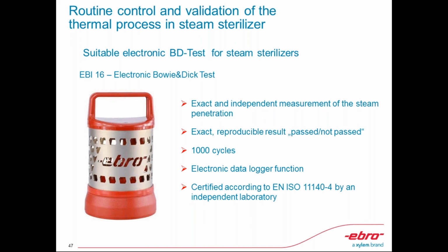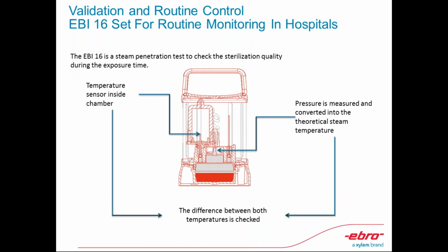And it is certified according to ISO 11140-4 by an independent laboratory. So the Bowie and Dick test logger, the EBI16, is simulating not only the towel pack test in the autoclaves, but also the heat penetration test and the temperature measurement inside the chamber, and also the pressure measurements as converted into theoretical steam temperatures. So it's like a 3-in-1 or 4-in-1 data logger.